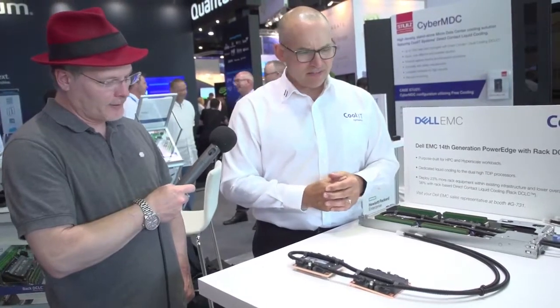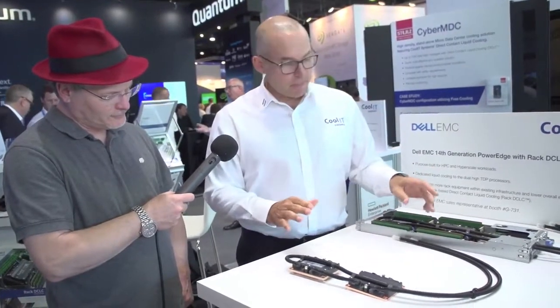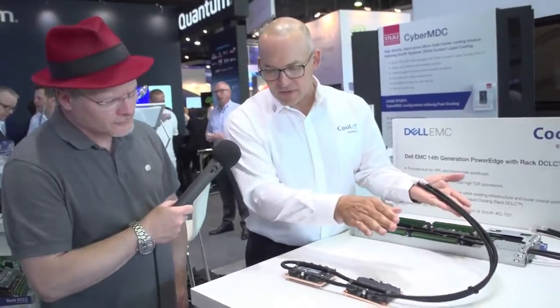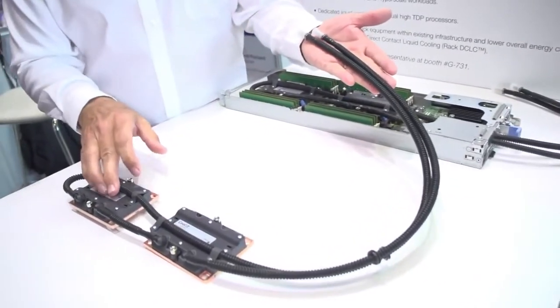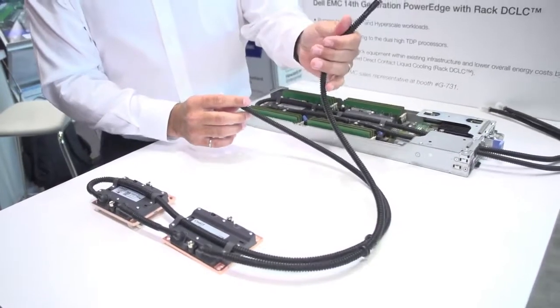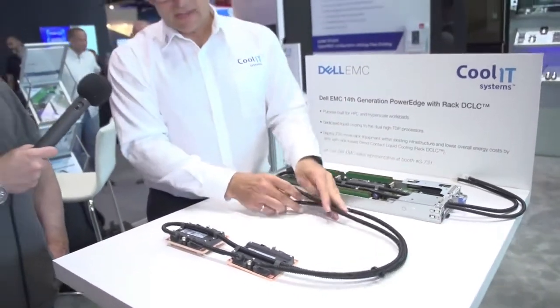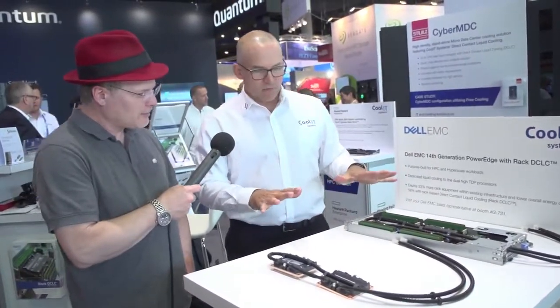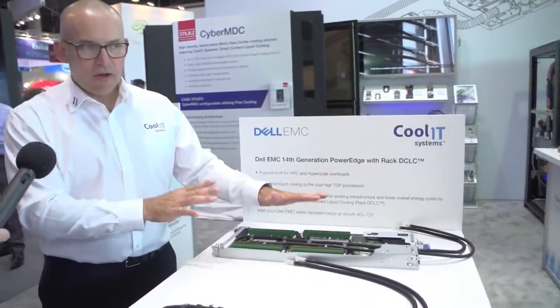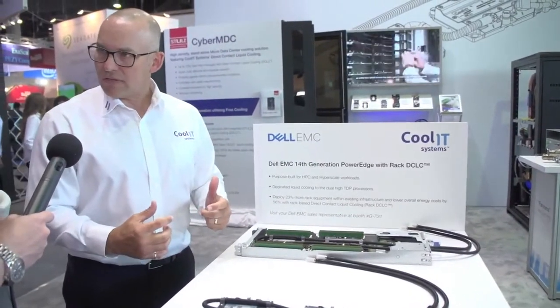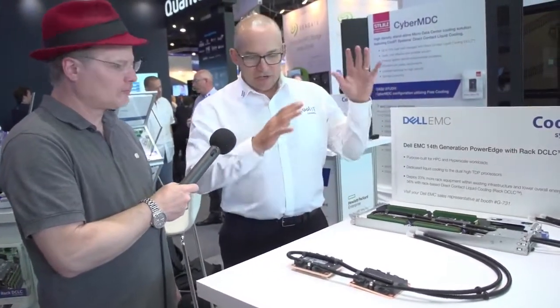I think the official release is just around the corner. Yes. So it's a rather simple setup. It gathers the heat off the processors, processor 1 then processor 2, and returns the warm water with the quick disconnect into the manifold. The program for Dell is set up so this module goes in the server, but we have standard manifolds that are now an orderable item through the Ingram Micro Dell S&P.